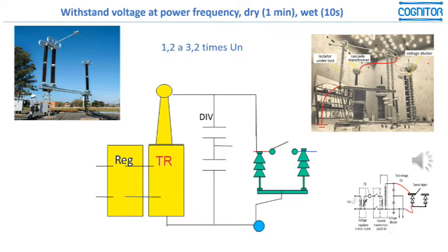Usually the voltage applied in the test, for the duration mentioned above, is the voltage prescribed in the standard for that level of rated voltage. The main objective of the test is to apply voltage to see if it will be supported without discharge, and just after the test you check that no discharge occurred, and in this case it is approved.